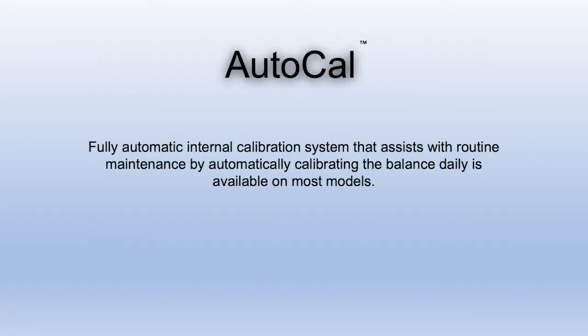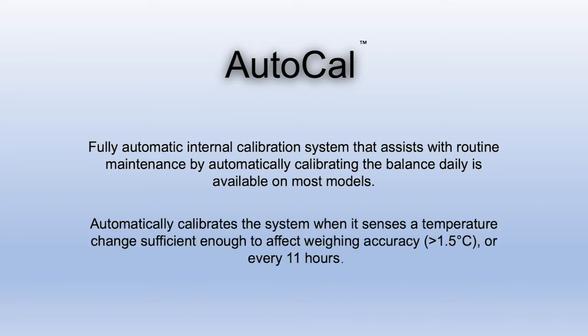AutoCal is a fully automatic internal calibration system that assists with routine maintenance by automatically calibrating the balance daily and is available on most models. It automatically calibrates the system when it senses a temperature change sufficient enough to affect weighing accuracy, which is greater than 1.5 degrees Celsius, or every 11 hours.